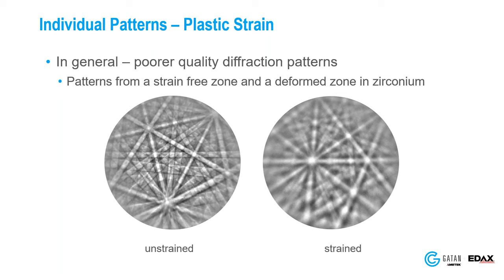Question: Why is a 70-degree sample tilt used? It's really about the electrons escaping. You can do EBSD flat, but so few electrons return to the detector and the patterns are much weaker. Seventy degrees is partly historical — from some of the first samples looked at, 70 degrees was a good geometry. You can operate at higher or lower tilts, but 70 seems to be a good balance and happy medium. Working at high tilt does create various distortions in the resulting images and makes the geometry more difficult to work with, but we get our best results at higher tilts.